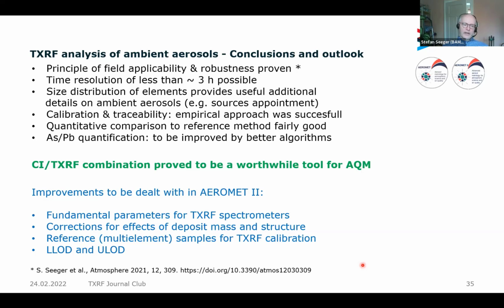In an ongoing project, the ongoing AEROMET II project, we work a lot on reference multi-element samples for a proper calibration, which also consider the influence of the deposit structure and probably overloading, and how we can determine the case of overloading of a sample, and are then able to determine whether a sample is good for TXRF analysis or has to be excluded because the material on it is simply too much.